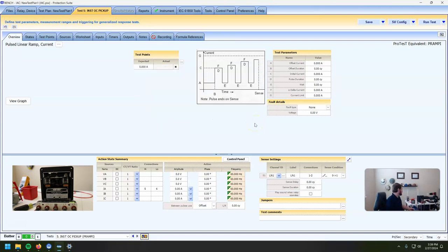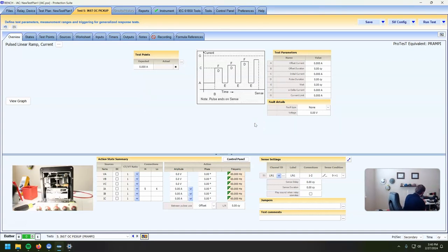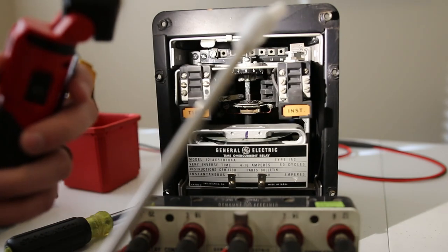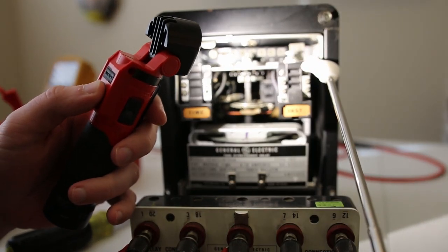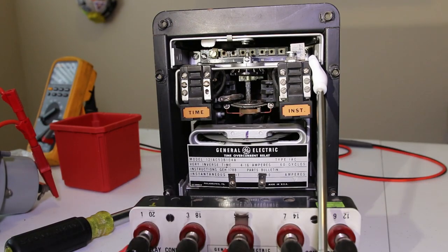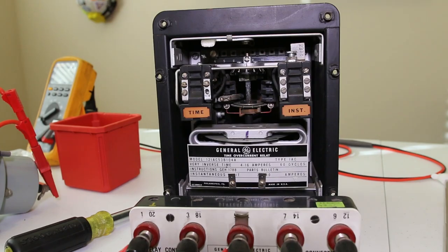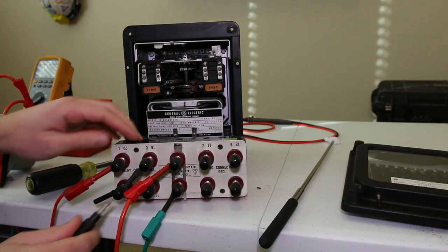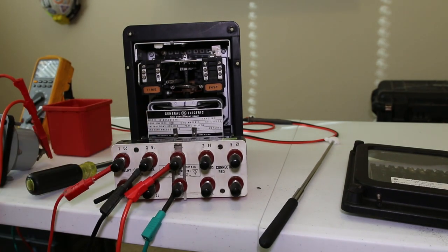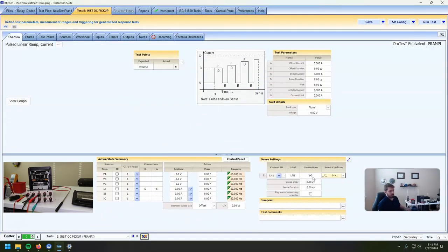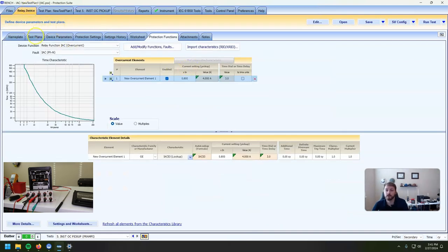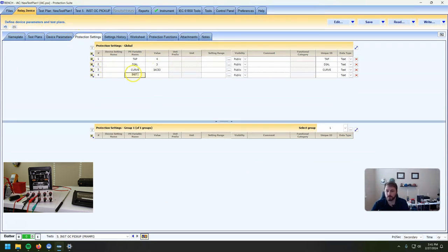This should be — looking over here, the top of that bolt looks to be right at 40. I do need to change our connections to one to three — that should be our instantaneous trip terminal connections. Our instantaneous setting is 40.